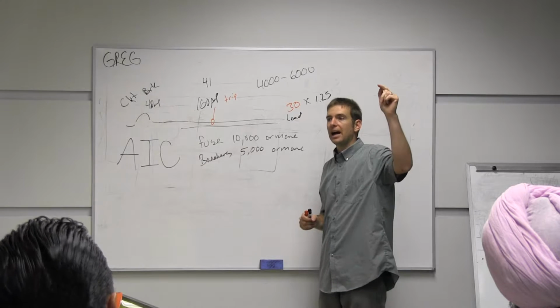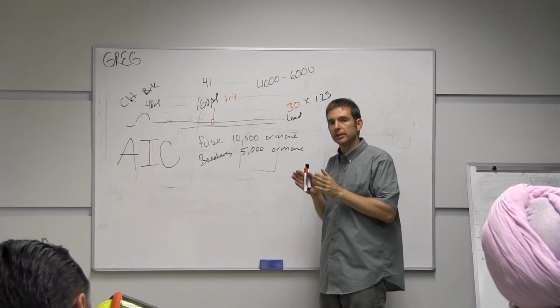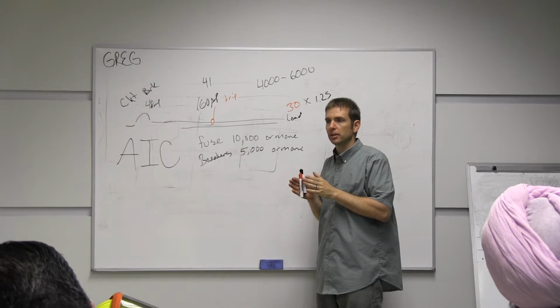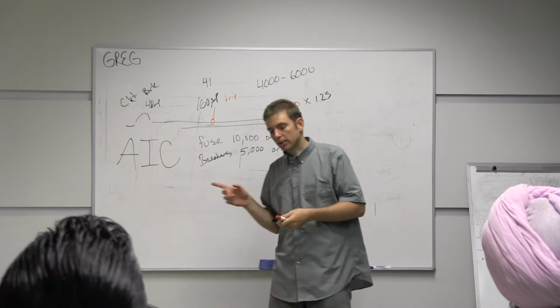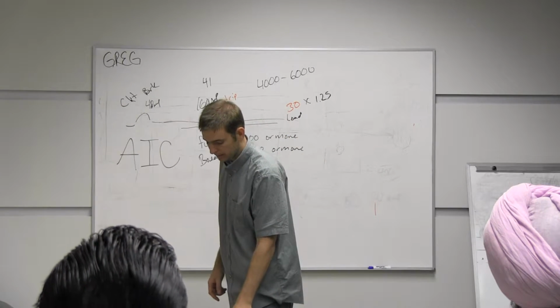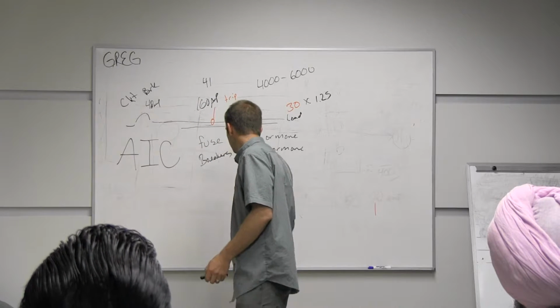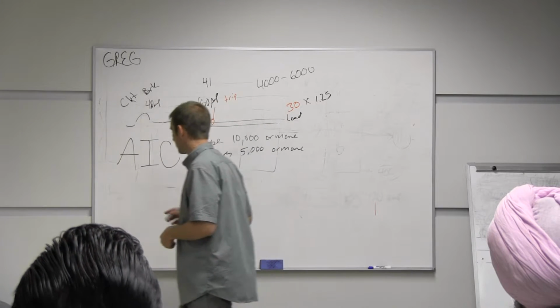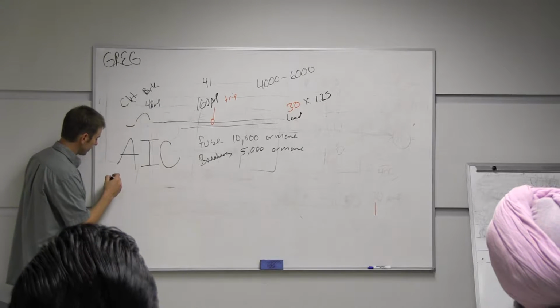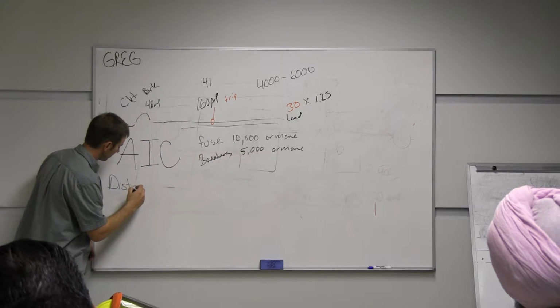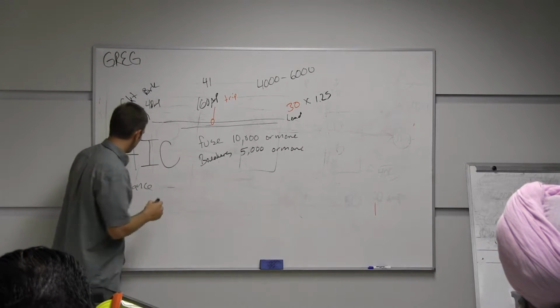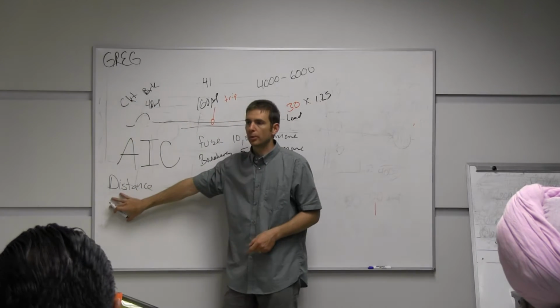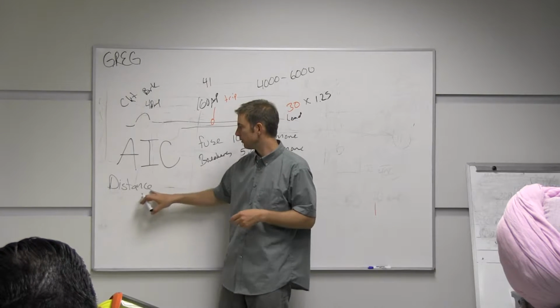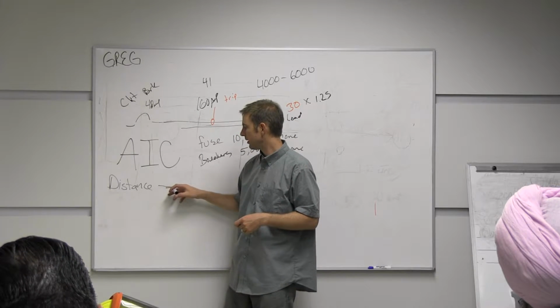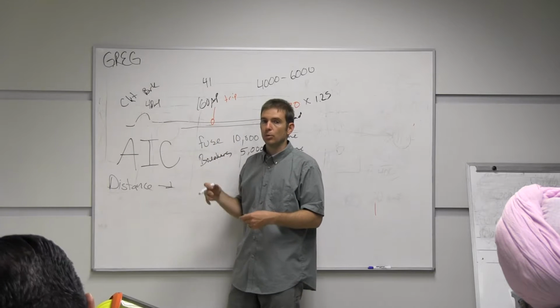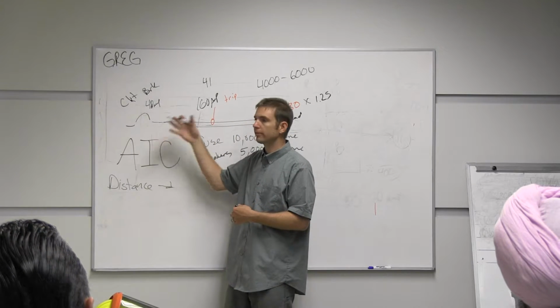But because you have high voltage panels and then a very short distance, you have your low voltage panels, that becomes a factor. What also becomes a factor is the size of your system. So if you have, here are some things to consider. Distance. The distance from your service or your transformers, from your high voltage side to low voltage side, the distance from there to where the arc flash occurs will depend on how much current flow is going to pass through.